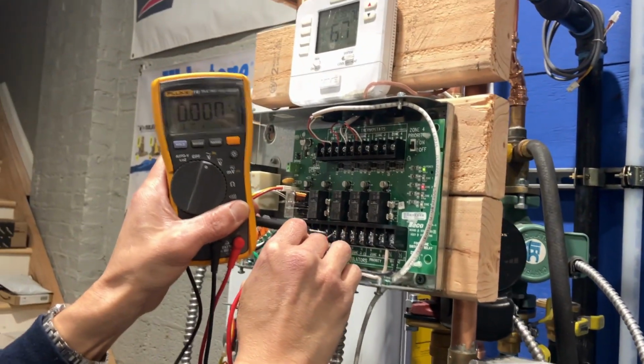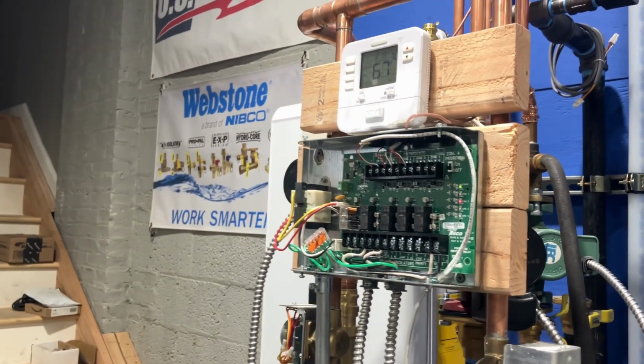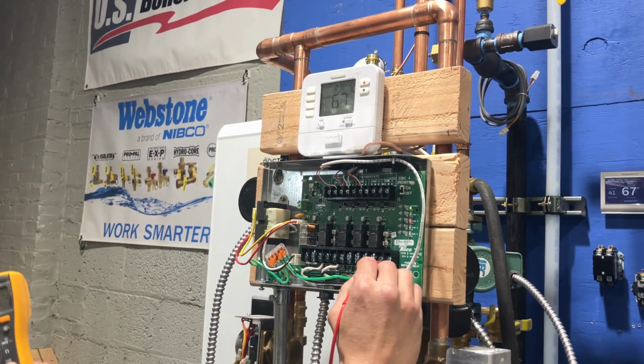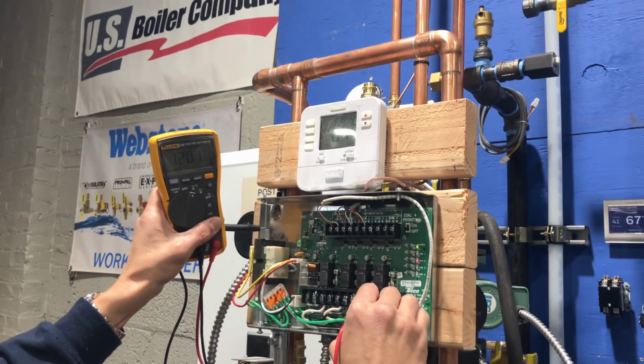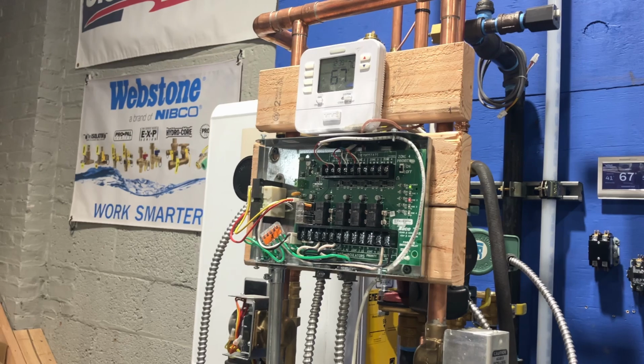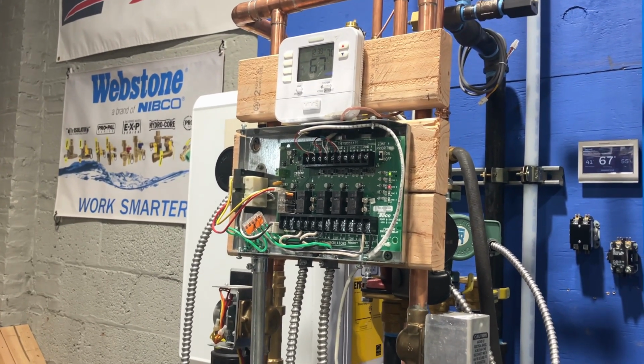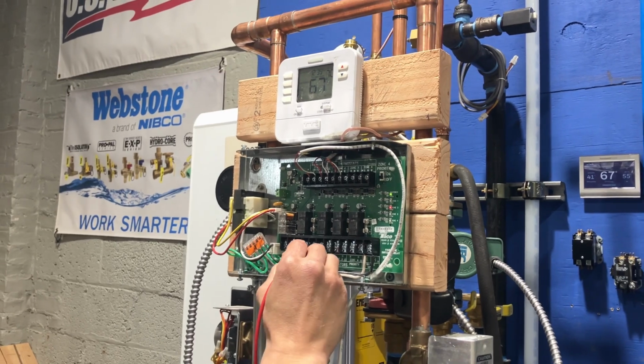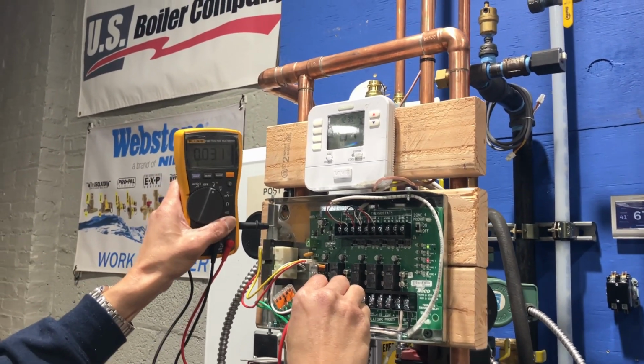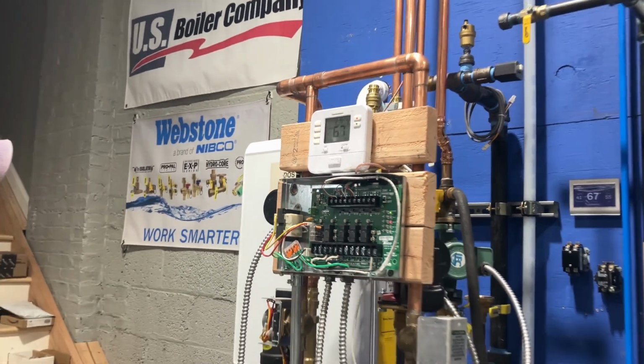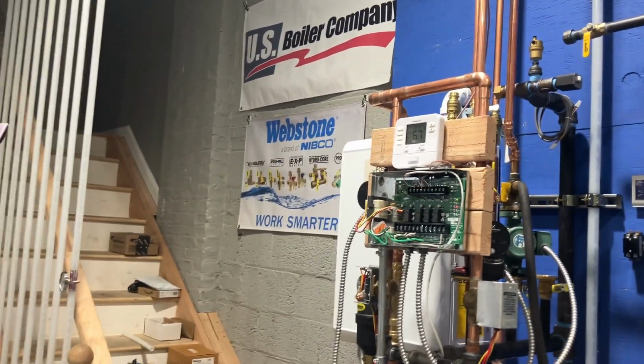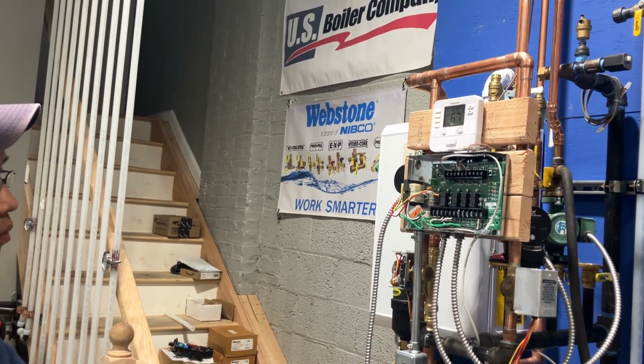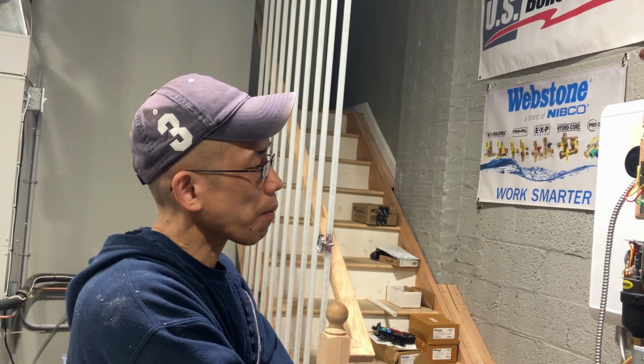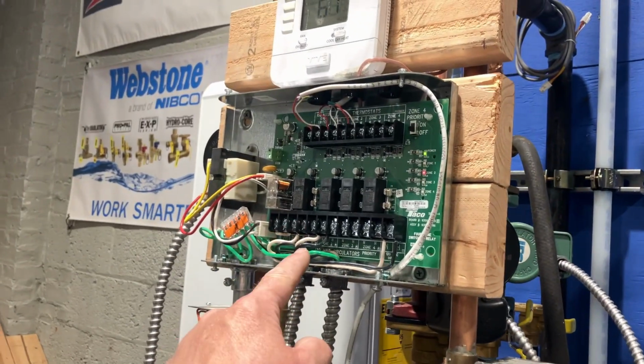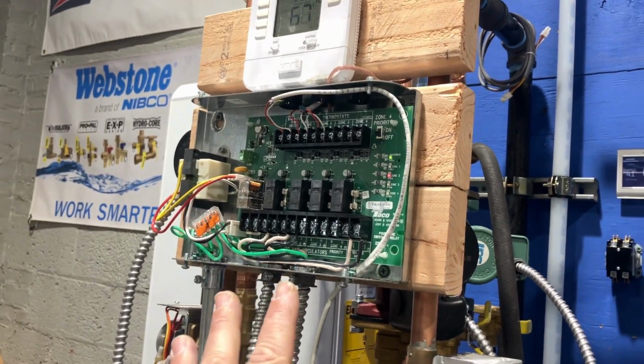So now I want you to check between the hot line and ground. On 120 volts there, that's a given. But for that circulator zone, you already have 110 volts there. Zone 2, hot and ground, sorry. You have no voltage there. Okay. So, let's say you did have voltage there. What are you going to check next? You have voltage to our circulator, right. Hypothetically. But the boiler's not turning on.